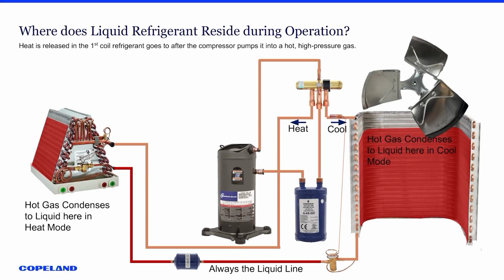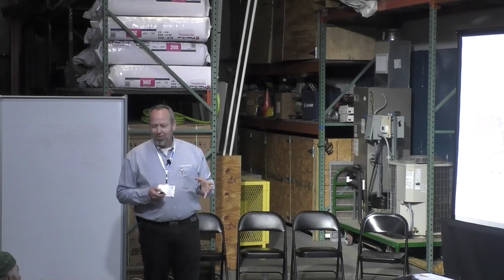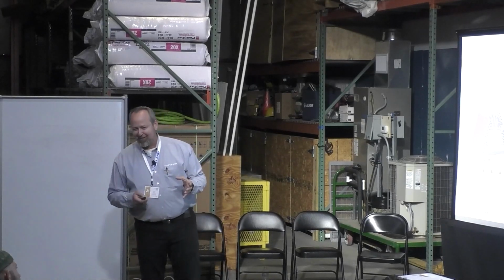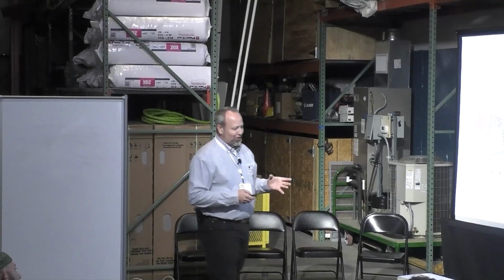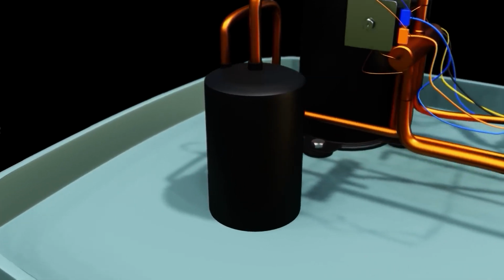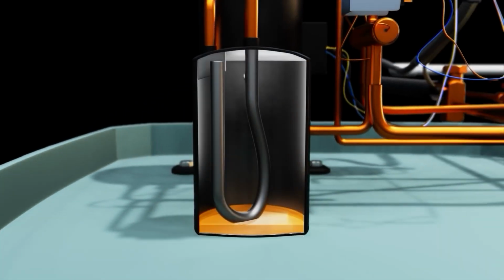What happens if there's some liquid that goes back through there? That's where the accumulator comes in. The accumulator is an additional device, or I don't know what the better word is, a canister really. A can is what it is. And if you were to look inside it, you would actually see a tube that goes all the way to the bottom and then comes back up most of the way.